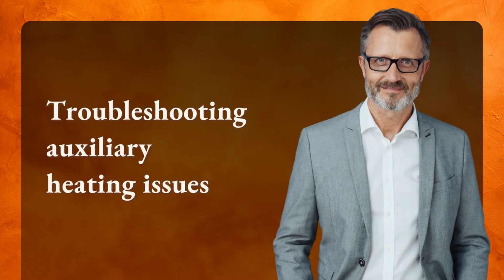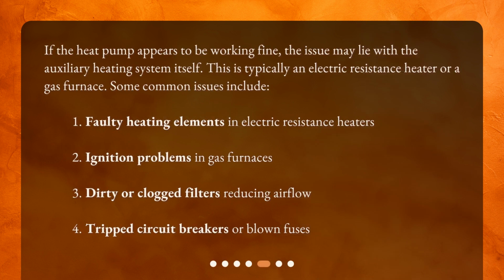Troubleshooting auxiliary heating issues. If the heat pump appears to be working fine, the issue may lie with the auxiliary heating system itself. This is typically an electric resistance heater or a gas furnace. Some common issues include: 1. Faulty heating elements in electric resistance heaters. 2. Ignition problems in gas furnaces. 3. Dirty or clogged filters reducing airflow. 4. Tripped circuit breakers or blown fuses.